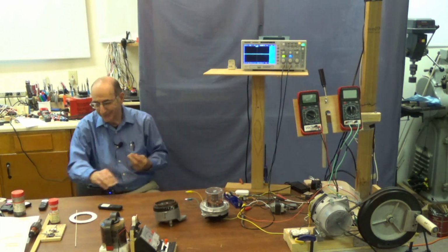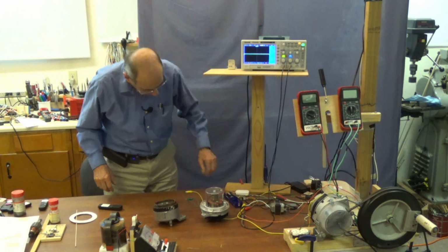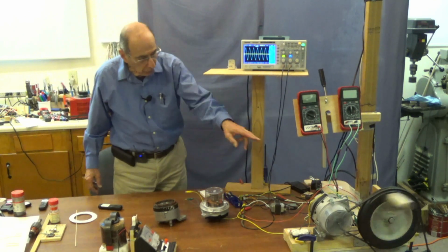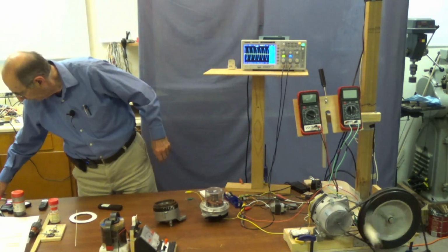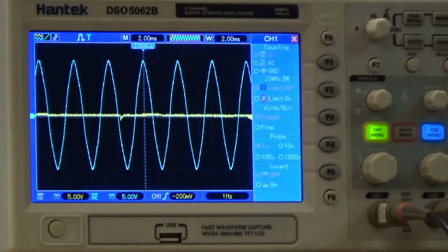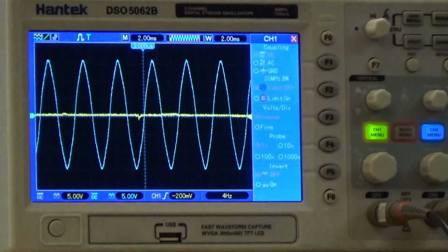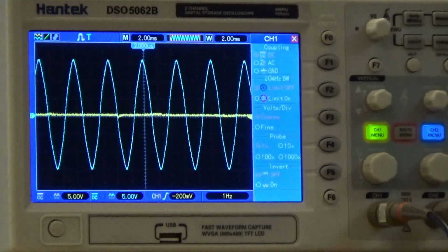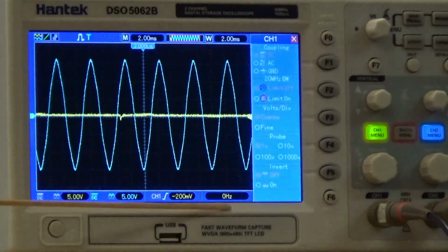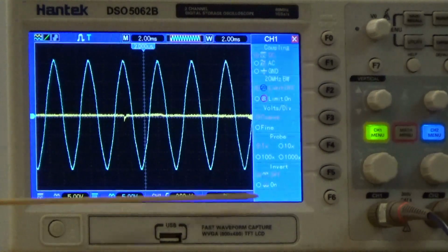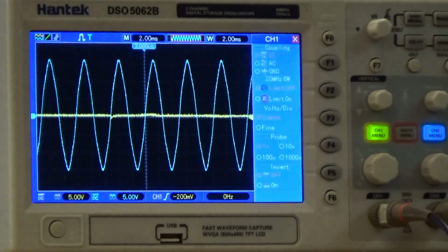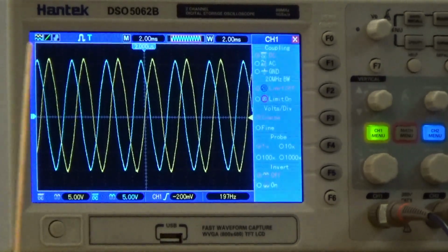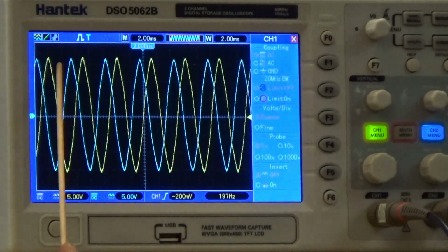Let's take a look at what that phasing looks like. Let's start up our alternator. So we're using that alternator, and what you're looking at is single-phase power, one of the 3 phases. Now, I can't show you all 3 because this oscilloscope only has 2 inputs. It only handles 2 channels. I'm going to add a second phase, and you'll see the second phase is in yellow. If I could do 3, it would end up right here in this gap.